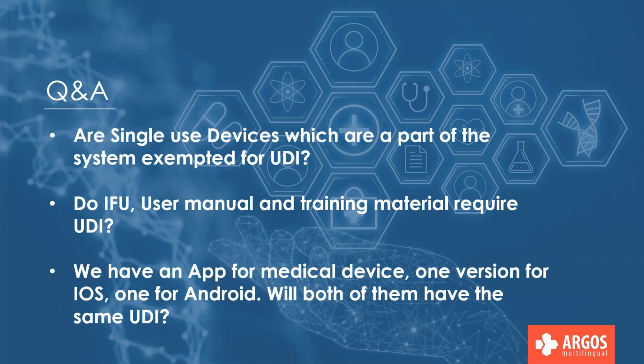But again, software as a medical device, or SiMD, software integrated in a medical device, I didn't get into a lot of detail here. So if you have further questions on that, I'd love to take a look at it for you and get into more detail. But just off the top of my head, just looking at this, I would say two different UDIs.